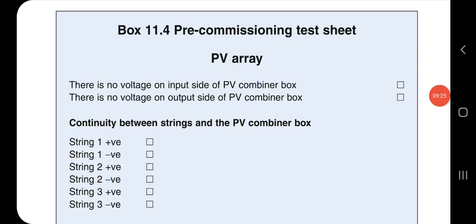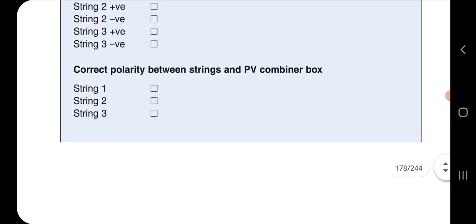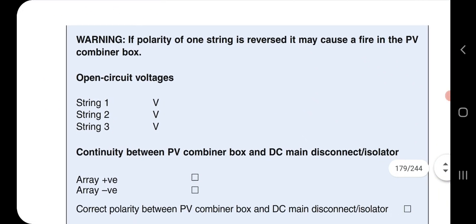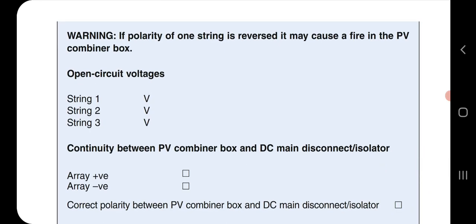So these are the various checklist test sheets, the pre-commissioning test sheet, which shows the continuity between string and PV box, string 1 positive and negative. All this has to be marked and checked properly. The correct polarity between string and PV box, this PV combiner box, has to be checked. So these are the sheets. Warning, in this one a warning is also there. The open circuit voltage of string 1, and strings 2 and 3, has to be calculated.